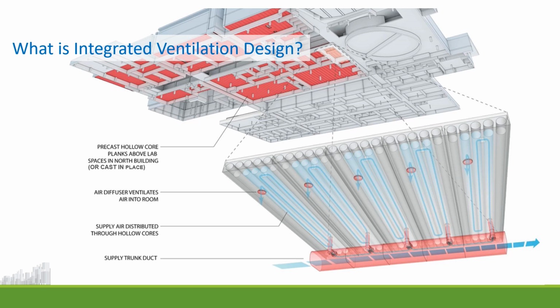Simple L ducts are used to connect the hollow core slabs with the ventilation, with serpentine ducting installed inside. These connect to the main HVAC duct and supply air into the building through a standard diffuser.